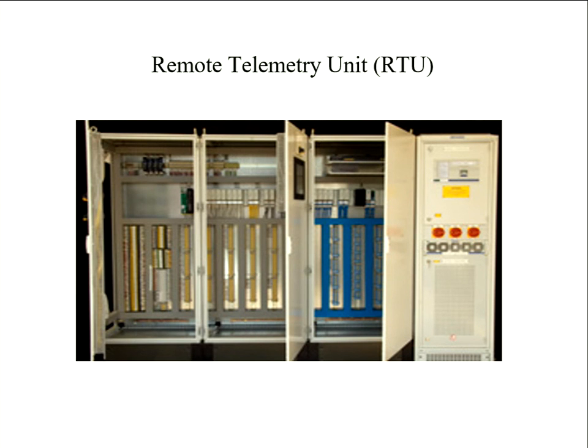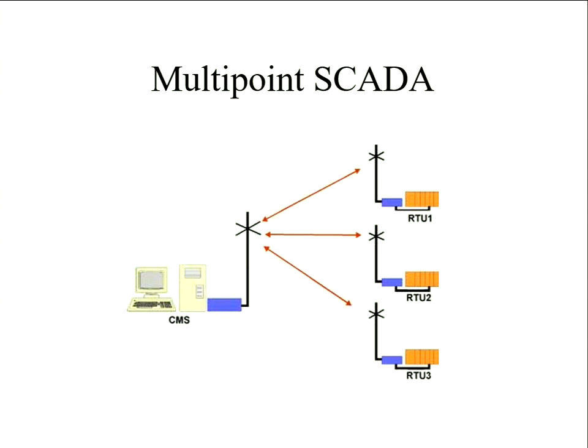Okay, most of the sites have got a certain amount of power backup, like batteries that will last for 24 hours, but I imagine they had a lot of fun the other day when Storm Doris came through, because I was on shift one Christmas day and a storm had gone through the previous night. You don't really want to call people out, but we had power alarms on so many sites, we had to get lots of people out, because usually the power had returned but it had tripped the local site power up, and if you'd have left it, the idea was you usually have enough backup on site till you can get a maintenance person there. So 8 to 24 hours, they're not designed to last indefinitely, these sites.